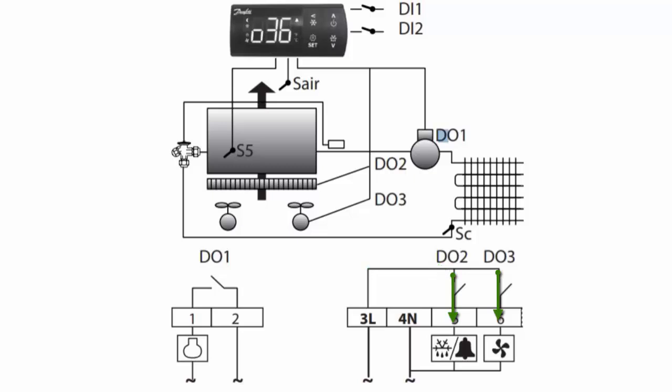It's a shared power supply, similar to the R terminal on your typical thermostat. Other terminals that feed different low-voltage devices - orange, yellow, and green - are all wet because they're fed from the same power supply that feeds the control itself.